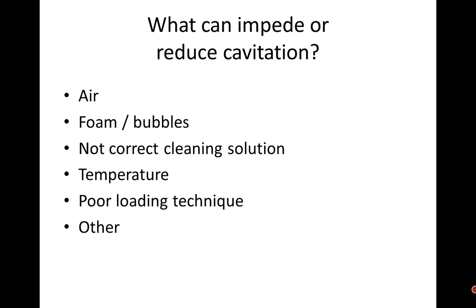Poor loading technique. That sonic could be working properly, but if you just throw the instruments in there and don't spread them out, distribute the weight appropriately, and open it up, you will not get effective cleaning by the sonic cleaner. And some other methods, again, draining of the tank, the soil that is left in the tank. If you're only doing it once a shift and you're running a lot of instruments through there, that soil stays in that tank, and that will impede the cavitation and impede the ability for your sonic to clean.